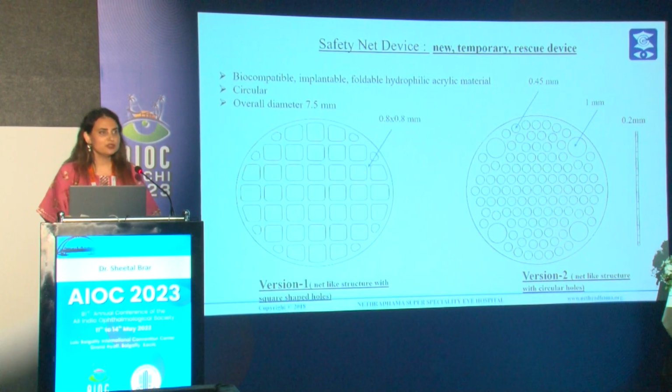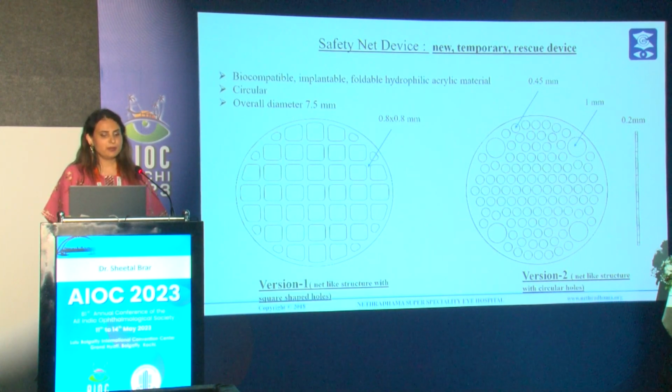So presenting to you a new device, we call it the safety net device, we have developed at Netradhama Eye Hospital. This is a new temporary rescue device made of biocompatible, implantable, foldable hydrophilic acrylic material. It is circular in shape and has an overall diameter of 7.5 millimeters.